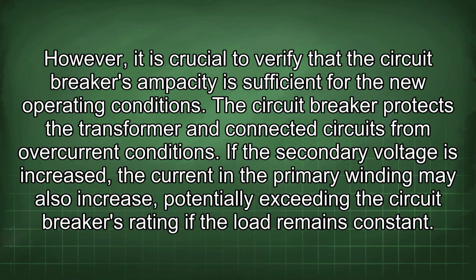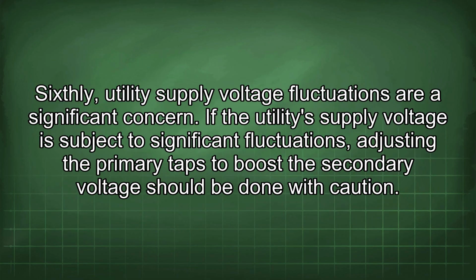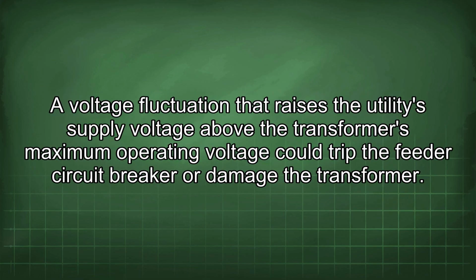If the secondary voltage is increased, the current in the primary winding may also increase, potentially exceeding the circuit breaker's rating if the load remains constant. Sixthly, utility supply voltage fluctuations are a significant concern. If the utility supply voltage is subject to significant fluctuations, adjusting the primary taps to boost the secondary voltage should be done with caution. A voltage fluctuation that raises the utility supply voltage above the transformer's maximum operating voltage could trip the feeder circuit breaker or damage the transformer.